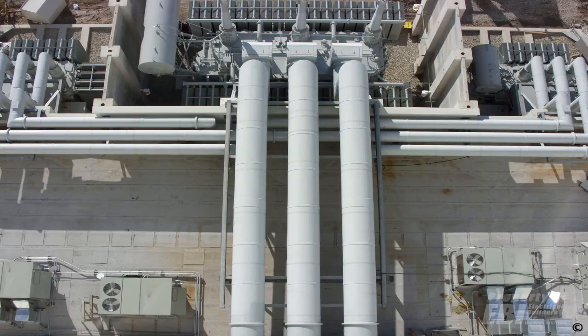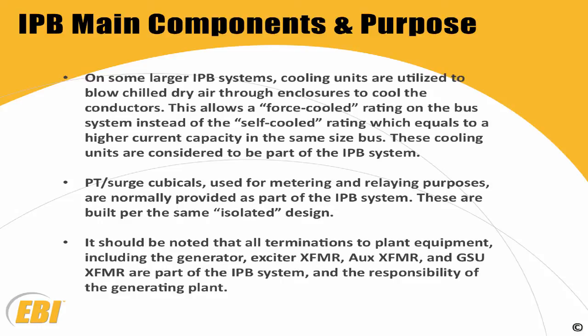This is a larger isolated phase bus system. It's just showing the bus where it goes out to the transformer. You've got a main GSU sitting in the middle with auxiliary transformers that tap off and are sitting on each side. On some larger IPB systems, you have a cooling unit that blows cool air through the enclosure that cools the conductor down. The conductor can only go up to 105 C as far as temperature is concerned. If you can cool the conductor down, it can carry more current.